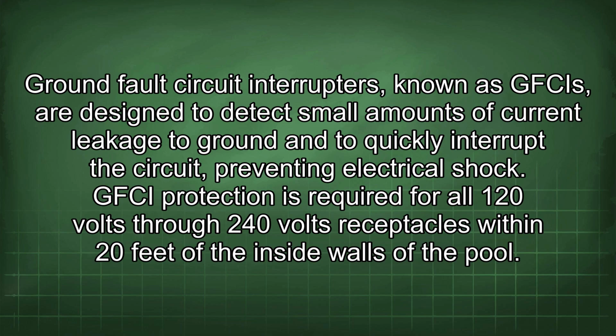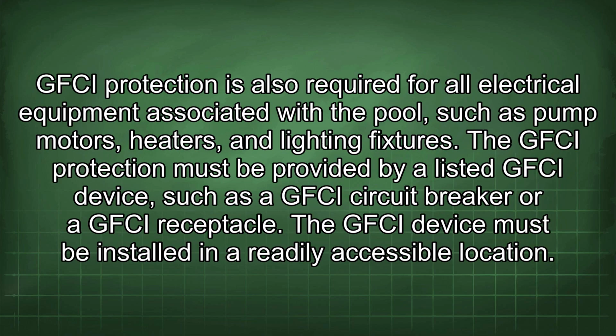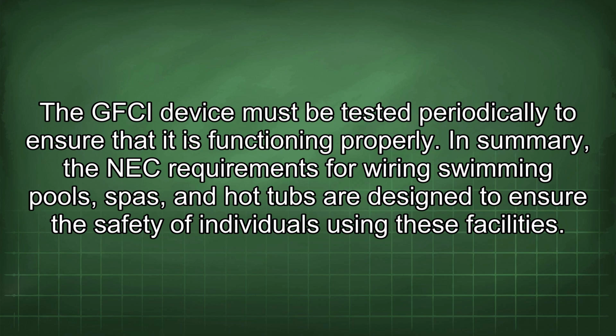GFCI protection is required for all 120 volts through 240 volts receptacles within 20 feet of the inside walls of the pool. GFCI protection is also required for all electrical equipment associated with the pool, such as pump motors, heaters, and lighting fixtures. The GFCI protection must be provided by a listed GFCI device, such as a GFCI circuit breaker or a GFCI receptacle. The GFCI device must be installed in a readily accessible location. The GFCI device must be tested periodically to ensure that it is functioning properly.